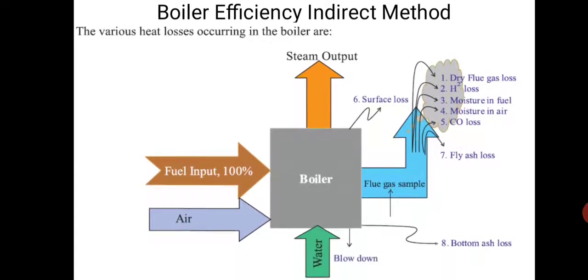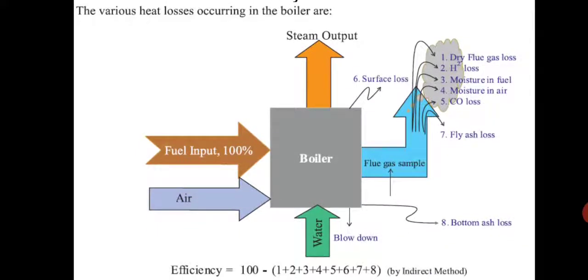For a boiler efficiency study, the fuel input and air are supplied, water goes in as steam comes out, and the flue gas losses are analyzed: dry flue gas loss, hydrogen loss, moisture in fuel, moisture in air, carbon monoxide loss, fly ash loss, surface loss, bottom ash loss, and blowdown. You study all these losses and subtract them from 100 percent — this gives the detailed efficiency of the boiler using the indirect method.